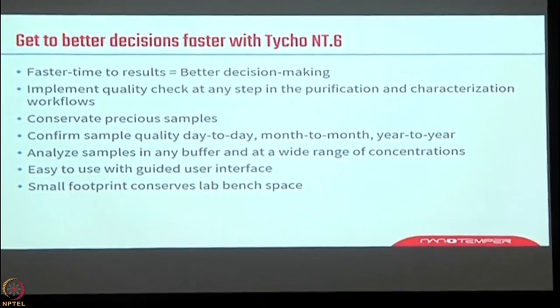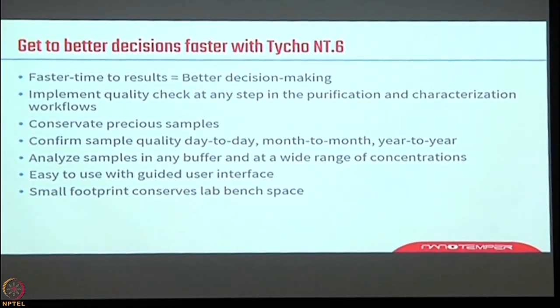The volume used is less than 10 microliters, and in one go you can analyze six samples in three minutes. The run rate is 30 degrees per minute. All our instruments are maintenance-free — there is no cleaning; you just put the capillaries in and take them off once the run is complete. The biggest benefit is it checks at the purification and characterization levels. You can check batch-to-batch samples, one-day-old versus ten-day-old samples, freeze-thaw cycles — and check actual purity, whether the protein has denatured or not.